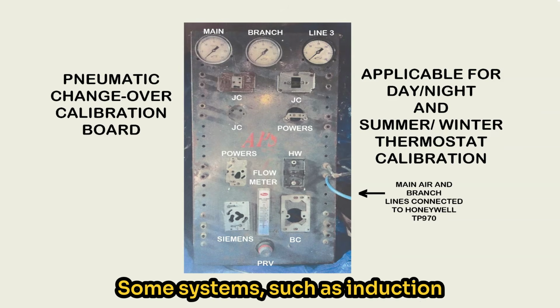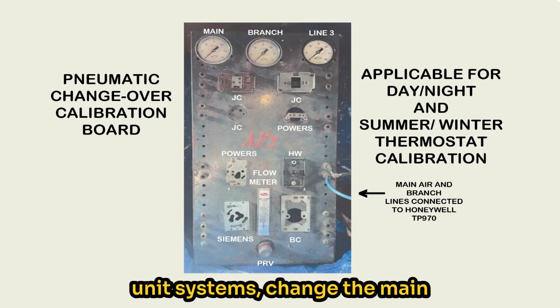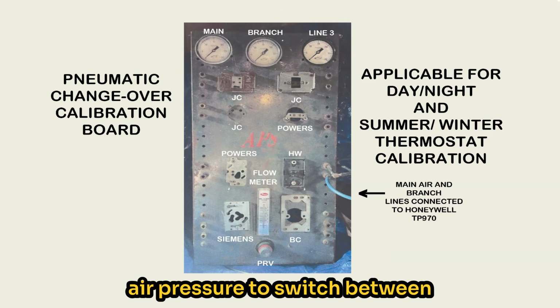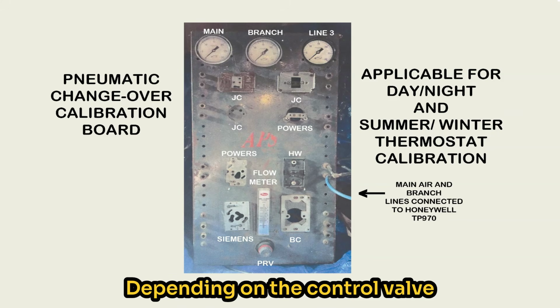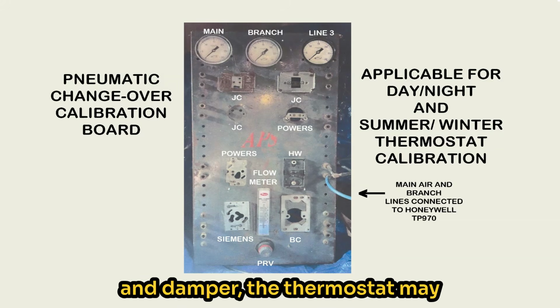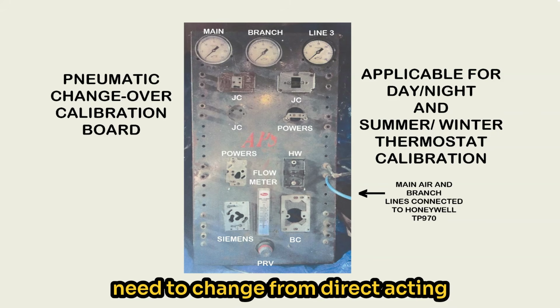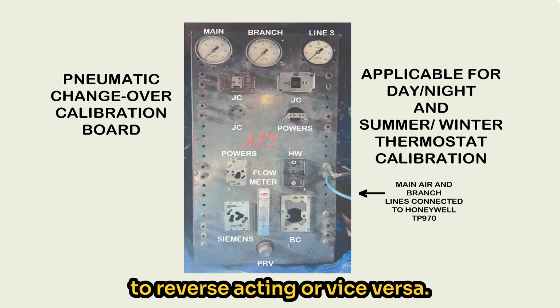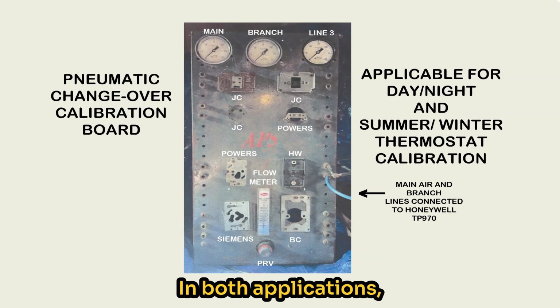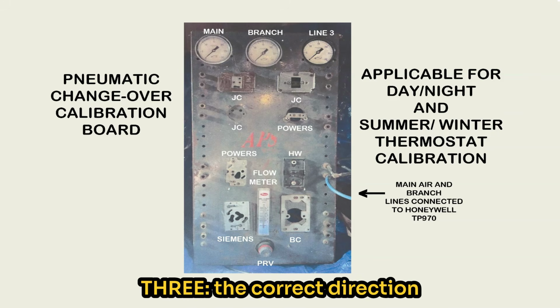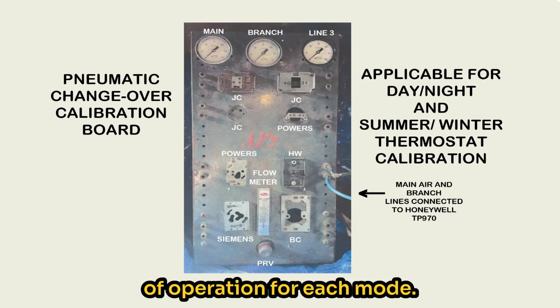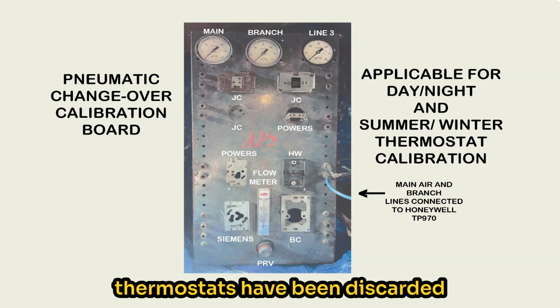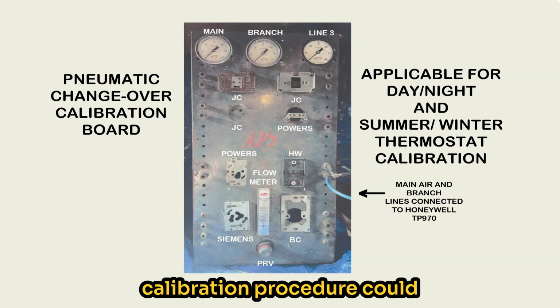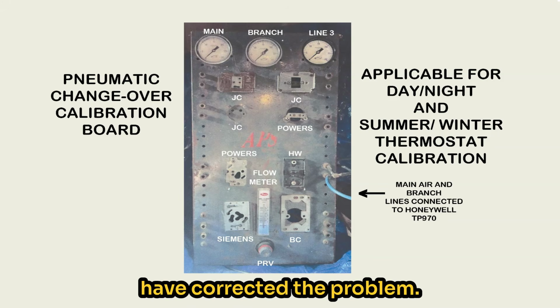Summer-winter systems. Some systems, such as induction unit systems, change the main air pressure to switch between summer and winter operation. Depending on the control valve and damper, the thermostat may need to change from direct acting to reverse acting or vice versa. In both applications, the thermostat must be properly calibrated for: 1. The temperature set points, 2. The correct changeover pressure, and 3. The correct direction of operation for each mode. Thousands of pneumatic thermostats have been discarded when a relatively simple calibration procedure could have corrected the problem.